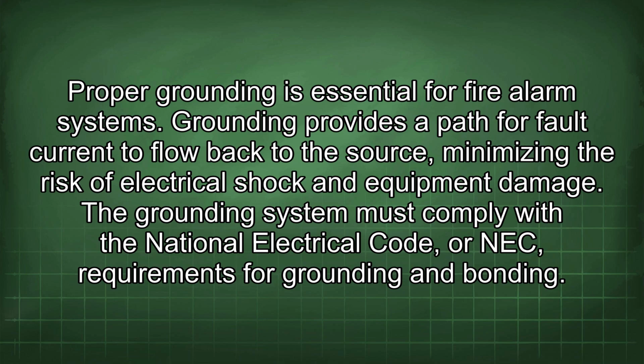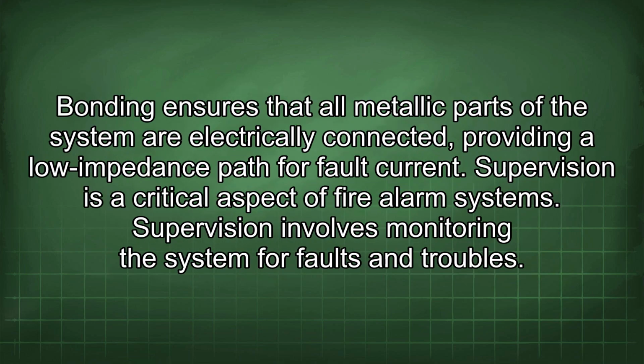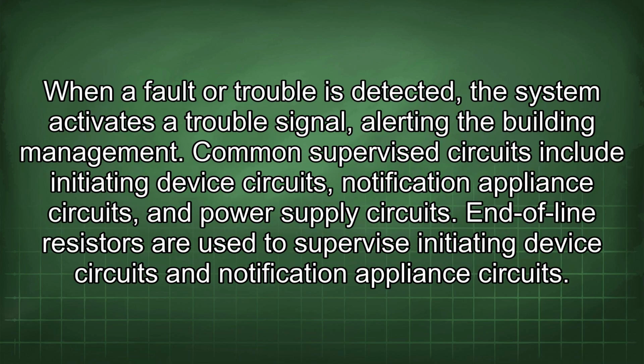The grounding system must comply with the National Electrical Code, or NEC, requirements for grounding and bonding. Bonding ensures that all metallic parts of the system are electrically connected, providing a low impedance path for fault current. Supervision is a critical aspect of fire alarm systems. Supervision involves monitoring the system for faults and troubles. When a fault or trouble is detected, the system activates a trouble signal alerting the building management.